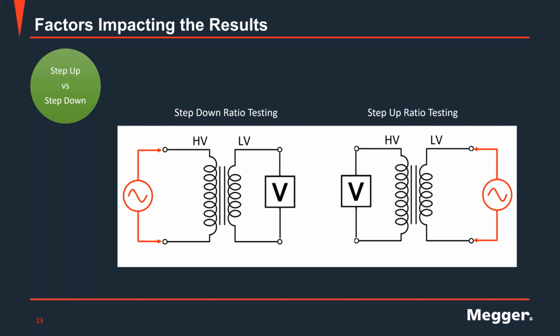When you have a unit that can do step up, right? Obviously the opposite, applying voltage on the low voltage side of the transformer and stepping it up to measure the induced voltage on the high voltage side. Well, that instrument is really important that it accounts for that higher voltage that it's going to induce, right?